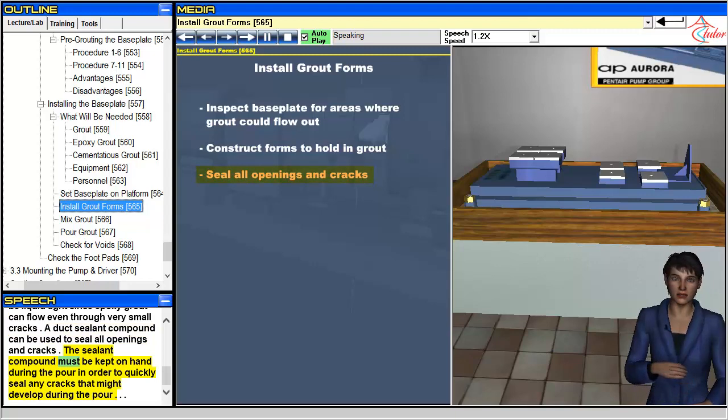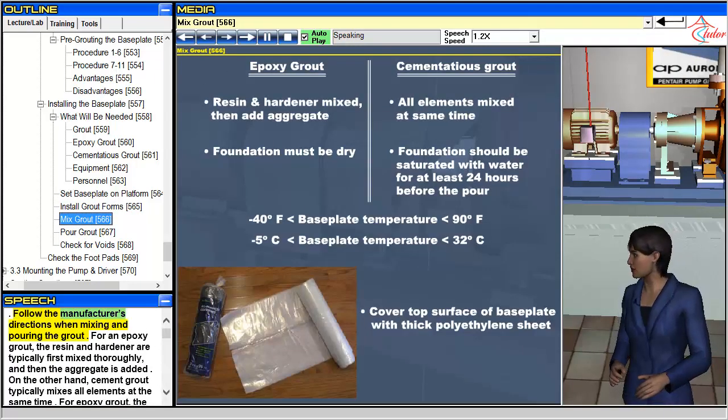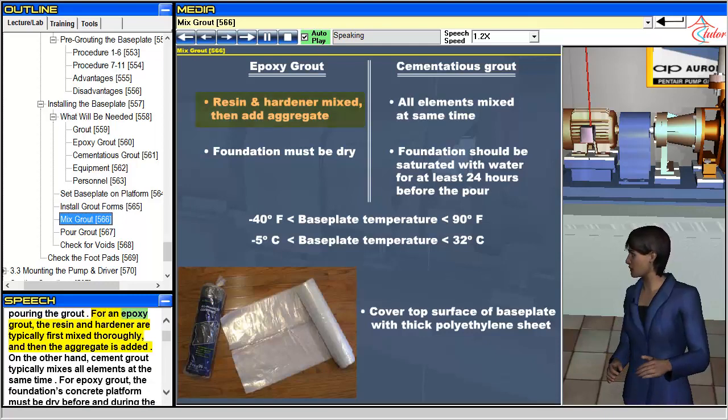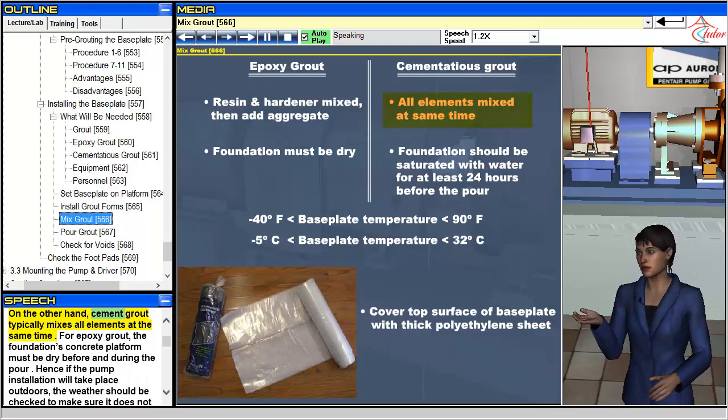A grout sealant compound can be used to seal all openings and cracks. The sealant compound must be kept on hand during the pour in order to quickly seal any cracks that might develop. Follow the manufacturer's directions when mixing and pouring the grout. For epoxy grout, the resin and hardener are typically first mixed thoroughly, and then the aggregate is added. Cement grout, on the other hand, typically mixes all elements at the same time.